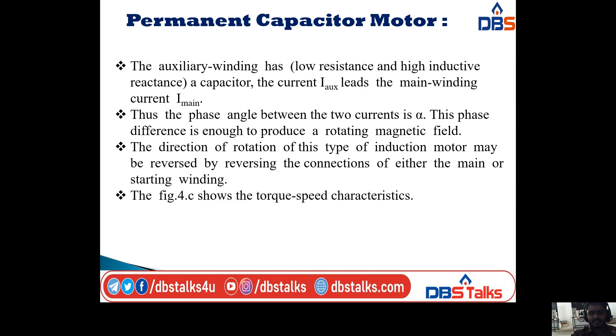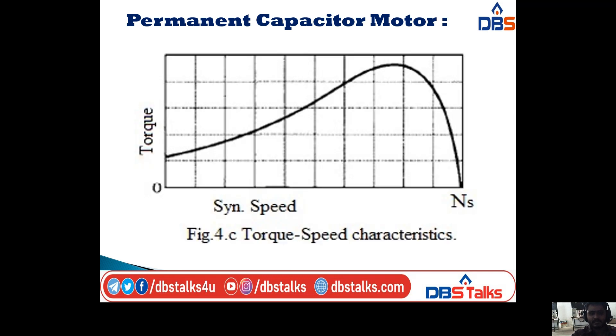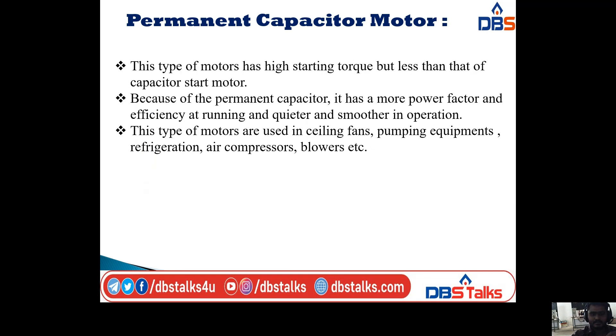The direction of rotation of this type of induction motor may be reversed by reversing the connections of either the main or starting winding. The torque-speed characteristics of the permanent capacitor motor are shown, with the graph drawn between torque and synchronous speed. This type of motor has high starting torque, but less than the capacitor start motor.